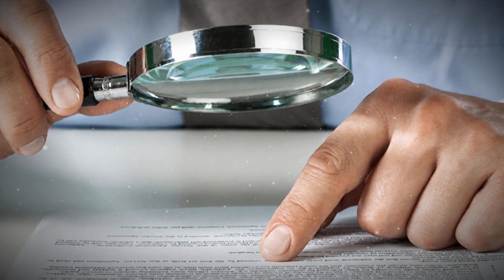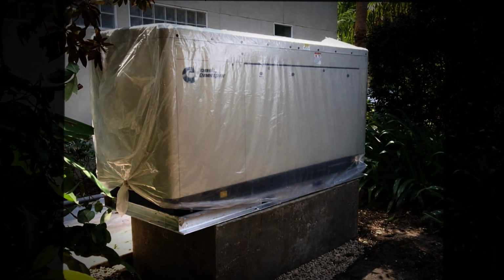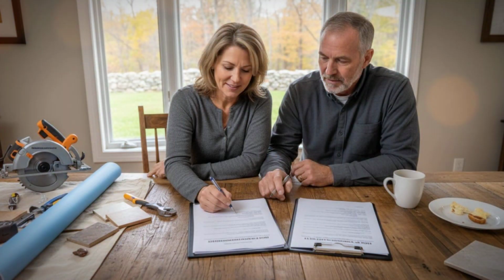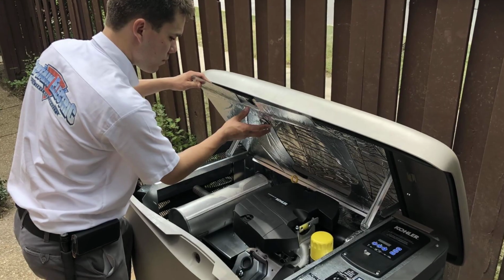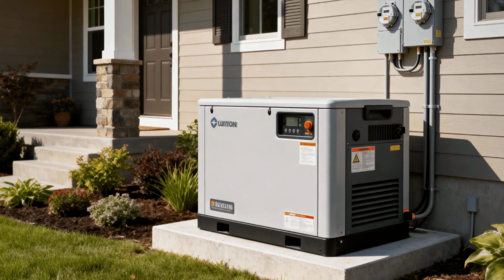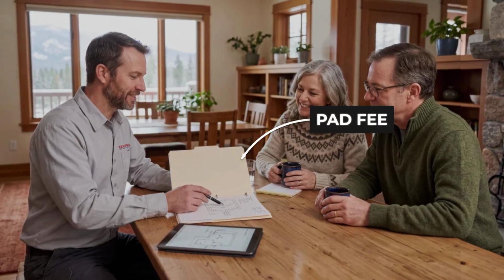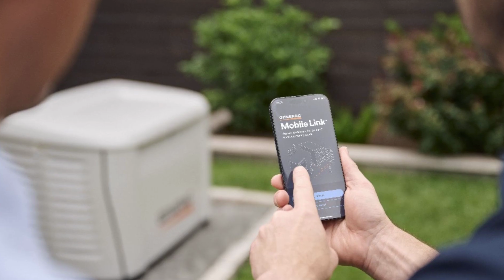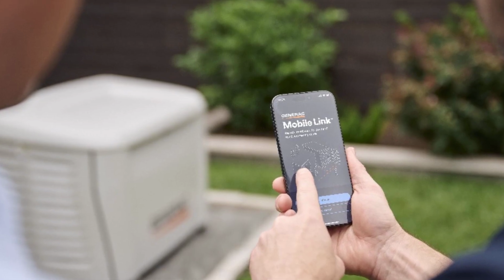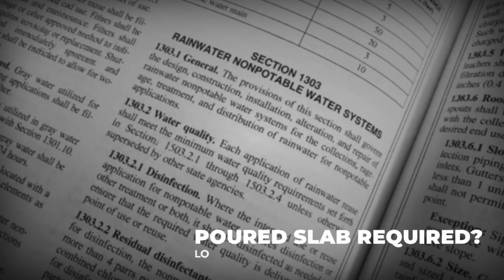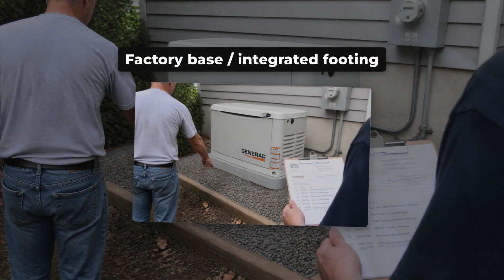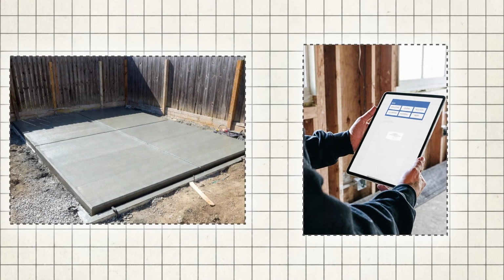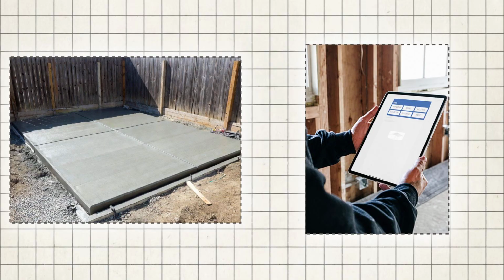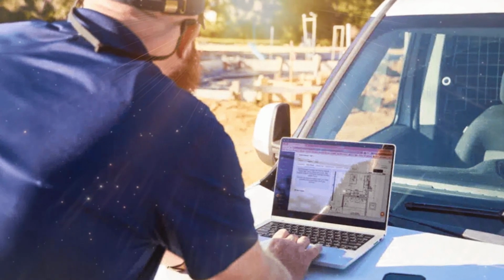Once when you bought the generator, and again when they bill you for a slab it doesn't need. That's the fee that even careful buyers miss, because concrete pads used to be standard on every single job, so nobody thinks to question it anymore. They just assume it's part of the process, the way it always used to be. Before you approve any pad line item on your bid, ask directly whether your specific model ships with a factory base, and whether your local code actually requires poured concrete underneath a unit that already has one. If the answer is that the generator already ships with what it needs, that line item should shrink dramatically, down to just gravel and leveling work, or disappear from your bid entirely.